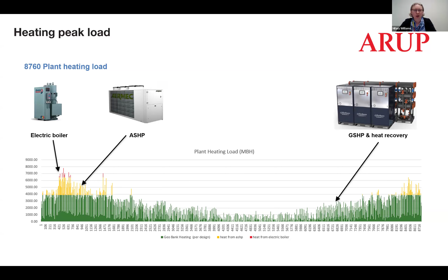So that's where the 96% demand figure comes from, even though, as you can see, maybe you can't see, the cutoff is 4,000 there in BTUs. So there isn't only 4,000 of capacity in that system, but that covers you for a large portion of the year. And then you go to a slightly less energy efficient solution, but also one that's a little bit easier to deal with peaks and troughs, and that's the air source heat pumps. And then for the least efficient, where you're using it for maybe less than 1% of your year, you're covering that with the electric boilers.